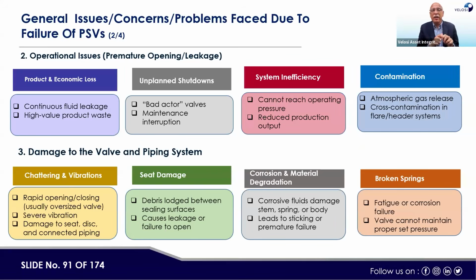Number one, it may lift at the given set point. This is the PSV purpose. The PSV is there, it should pop up if pressure goes more than a certain limit. However, what happens if the PSV lifts prematurely? It will cause the shutdown of the plant, because the PSV has lifted when it should not be lifting. Secondly, what can happen? The PSV is leaking. It means you are wasting the product to the flare line.